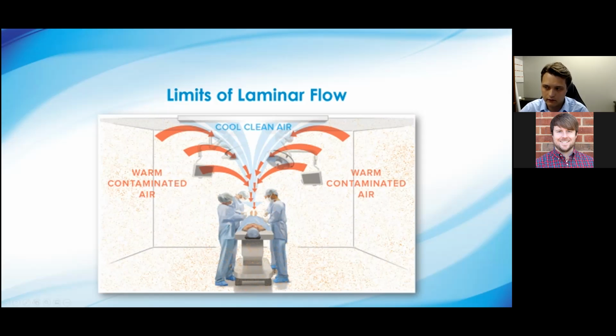The other side effect of this is the patient is now receiving the brunt of the cooling. On average, what we've seen is about a 6 or 7 degree difference in temperature between the patient and the surgeon in terms of air temperature, because the patient is receiving the brunt of this cooling and it's actually moving very, very fast by the time it gets onto the table. It leaves the ceiling at about 25 feet per minute, and it's about 125 to 150 feet per minute by the time it gets down to the patient. Meanwhile, the surgeon isn't feeling any of that direct cooling effect because the air is just missing them.